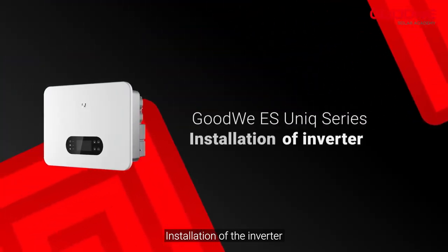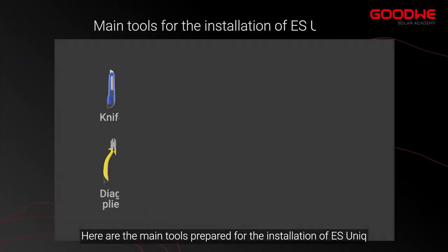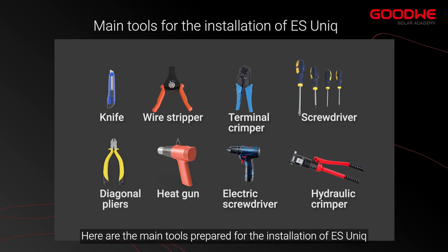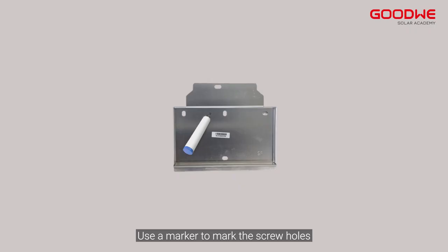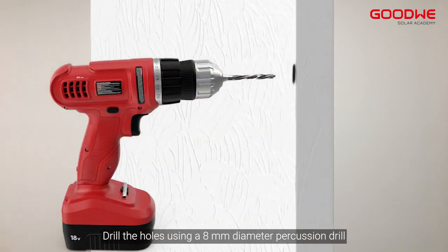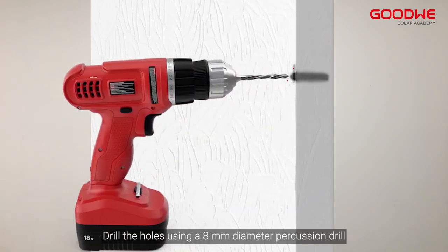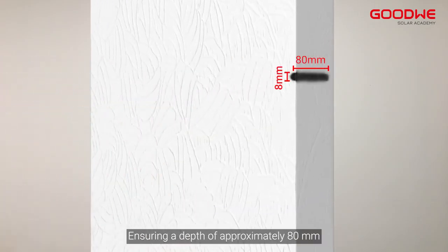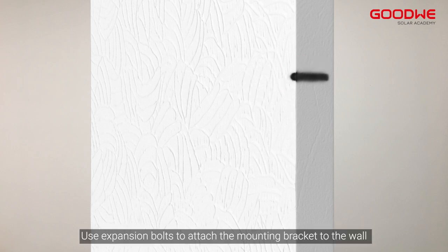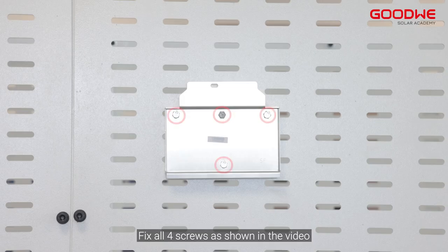Installation of the inverter. Here are the main tools prepared for the installation of ES Uniq. Use a marker to mark the screw holes. Drill the holes using a 8 mm diameter percussion drill, ensuring a depth of approximately 80 millimeters. Use expansion bolts to attach the mounting bracket to the wall. Fix all 4 screws as shown in the video.